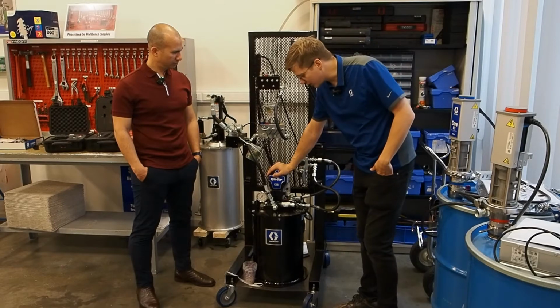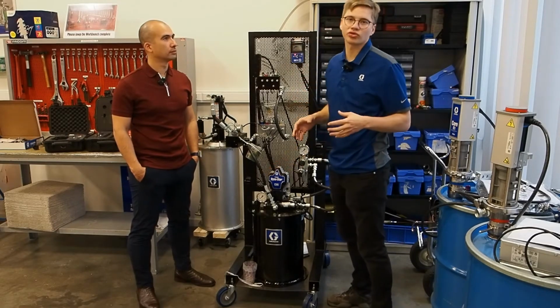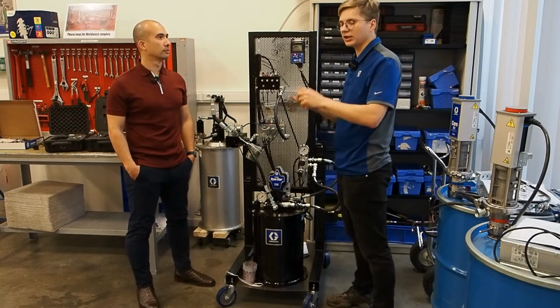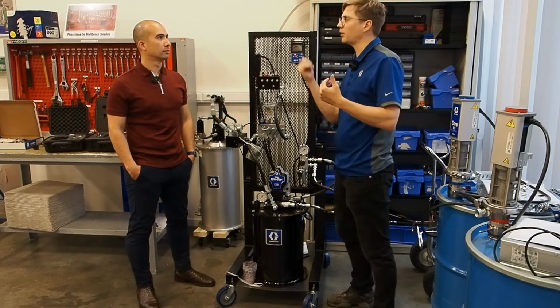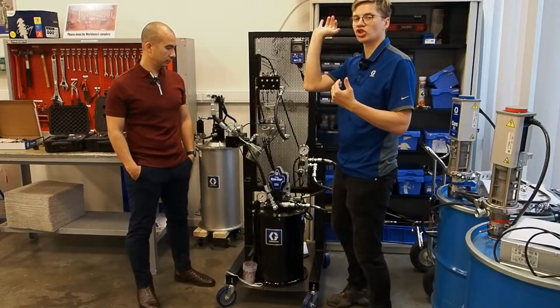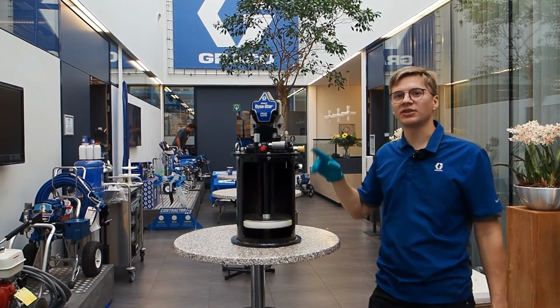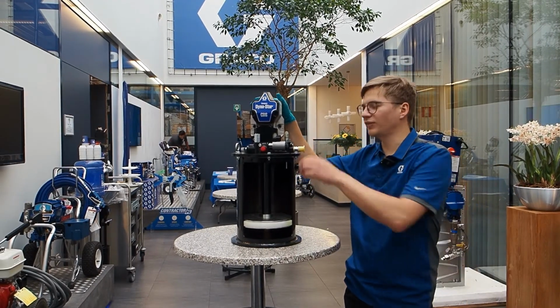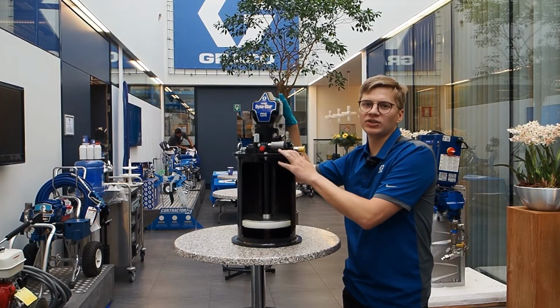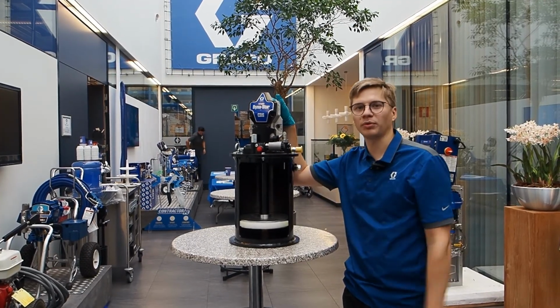So the compact Dynastar pump has a tube-in-tube construction, meaning that there is an inner tube and the outer tube. The inner tube is the tube where the pressure is being built up, and the pump builds up the pressure in a line. But this is the compact Dynastar. This is the 12-liter version of that pump. So we have 12 liter, 20 liters, and 27 liters, which is the most popular in mining.